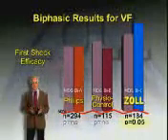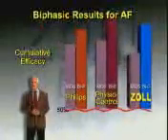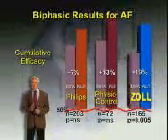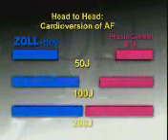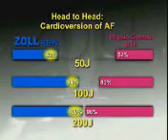Three studies, three waveforms, one was superior. Three more separate clinical trials of atrial fibrillation compared the same biphasic waveforms to the common standard monophasic damped sine waveform. Only Zoll shows statistically superior efficacy for cardioversion of atrial fibrillation. Again, three studies, three waveforms, one was superior. And in a head-to-head comparison with Physio Control at 50, 100, and 200 joule settings, Zoll stands out again, demonstrating higher efficacy with less energy.